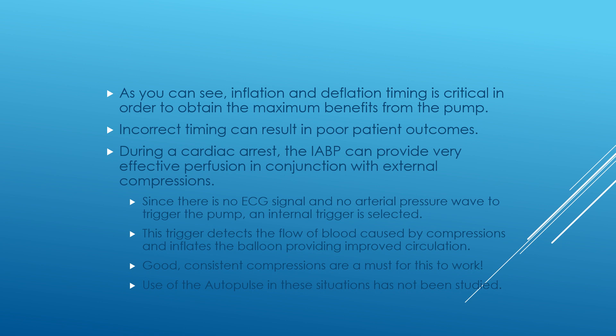During a cardiac arrest, the intra-aortic balloon pump can provide very effective perfusion in conjunction with external compressions. Since there is no ECG signal and no arterial pressure wave, the internal trigger is selected. The trigger detects the flow of blood caused by compression and inflates the balloon, providing circulation. Good, consistent compressions are a must for this to work. Use of the auto-pulse in these situations has not been studied.